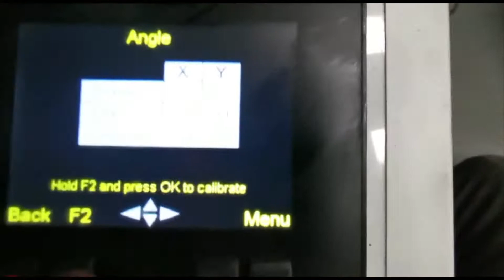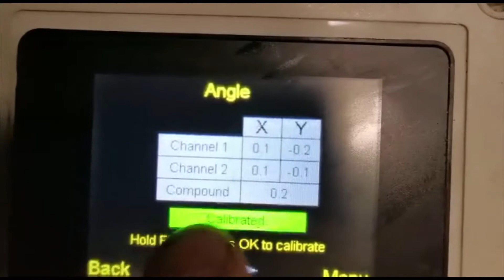F2. So you have to press and hold F2 here and press OK at the same time. So let me focus. Yeah, F2 OK, hold it. Now I have to type in the password. So I will use my own password. So when the password is accepted, then it's showing you that it's calibrating. See here, and it's showing it's calibrated.